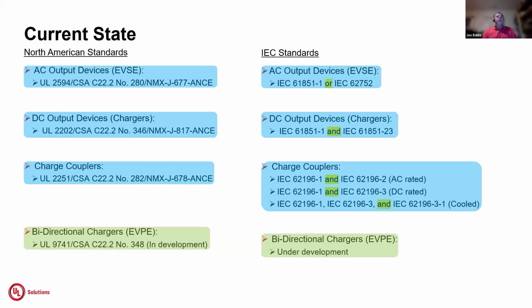But for bidirectional chargers, we have what's referred to as UL 9741, which is essentially taking the EV as a distributed energy resource and using grid interactive inverter requirements from UL 1741 to tie it to the grid. That is currently being harmonized with Canada, which will be CSA 348.